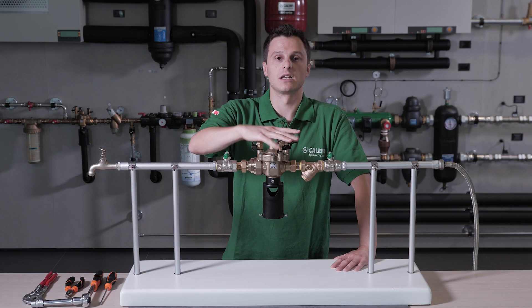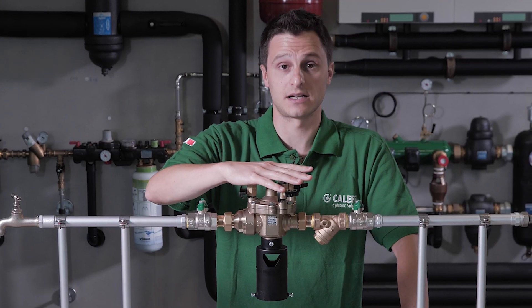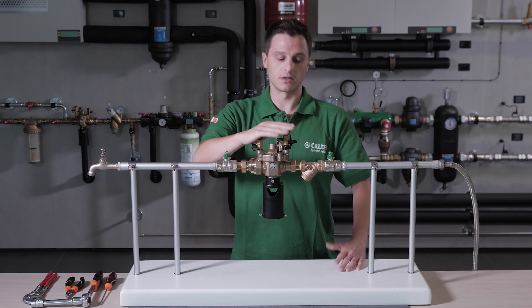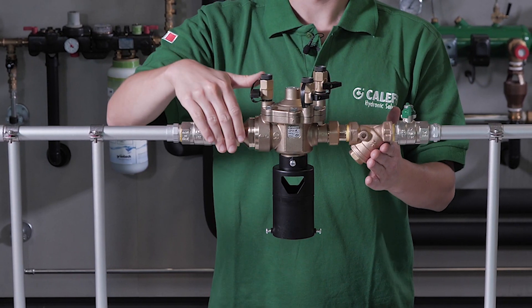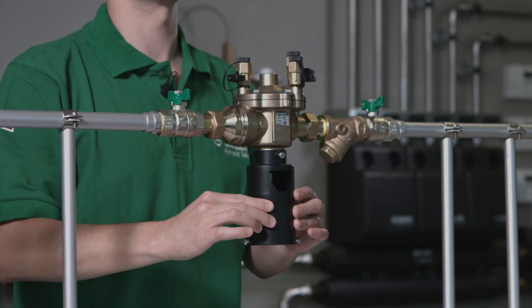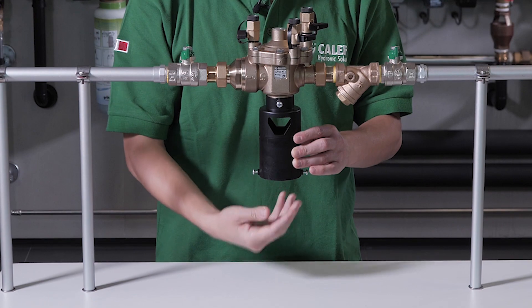The backflow preventer installation point must have easy access. The backflow preventer must be installed in a horizontal position and its discharge line connected with a discharge pipe.